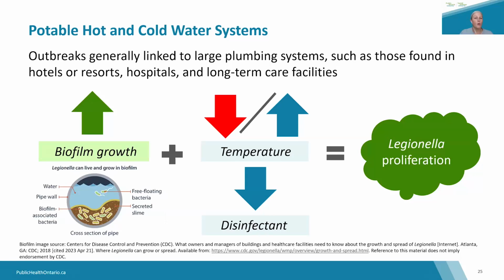There can also be old plumbing that can be a concern, as it can experience corrosion and scaling that can lead to biofilm. There can be heat transfer due to uninsulated pipes that can lead to temperature decreases of hot water, but can also cause temperature increases in cold water, providing those favorable temperatures for Legionella growth. Poorly insulated water tanks can also lead to these temperature fluctuations. There can also be redundant pipework or dead legs or dead ends in the plumbing, and this can lead to stagnation of water, again, allowing for biofilm growth and biofilm to establish.